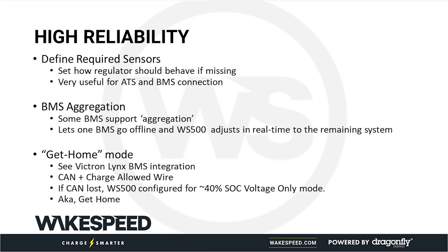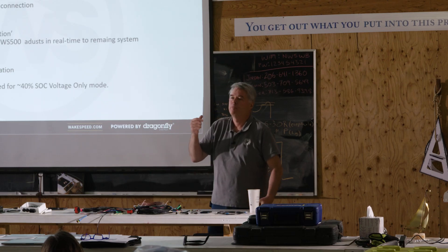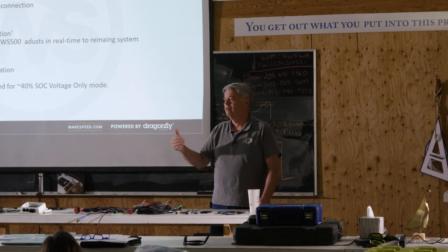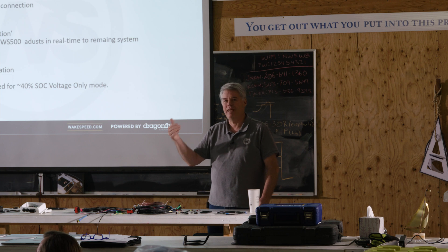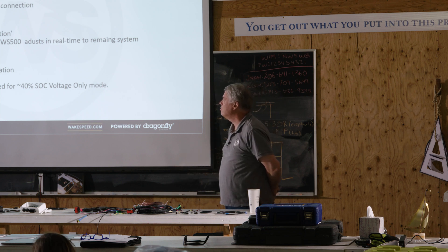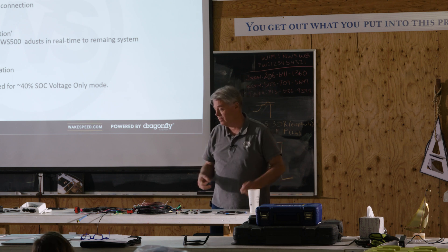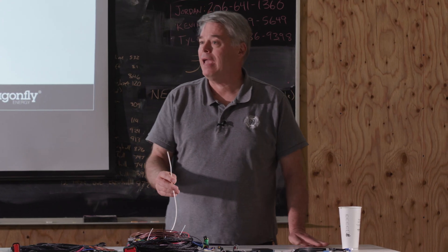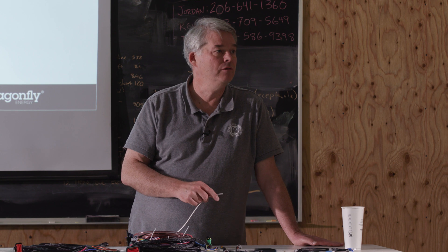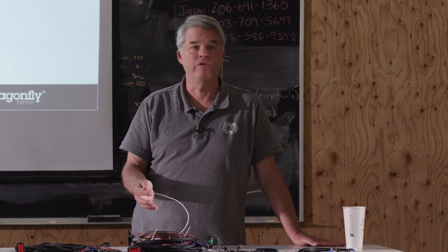Get home mode is another interesting advanced high-reliability feature, and it's kind of a two-edged sword. When you put these advanced features in and operators are running and they enable without understanding what happened, they're going to say 'What's wrong? Why is this thing not working?' We have get home mode defined for the Victron Lynx BMS, and you could do other BMSs as well. The question is: if we depend on the CAN-connected BMS for our information, what do you want to have happen if that BMS goes away and we lose that connection?